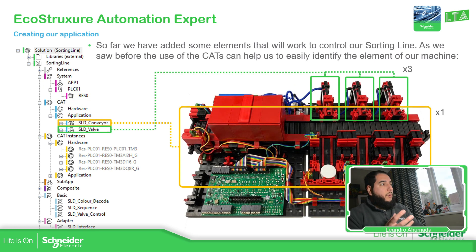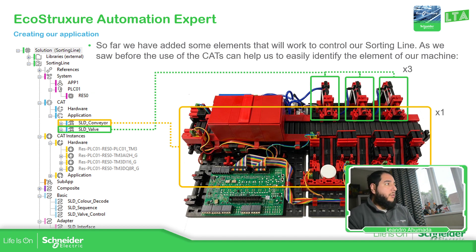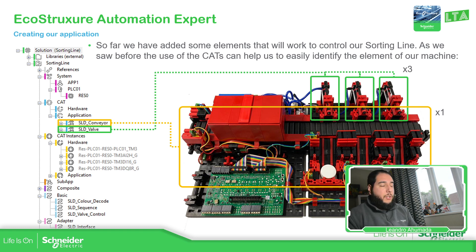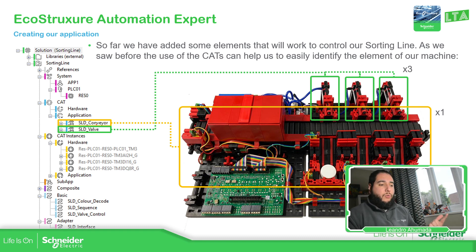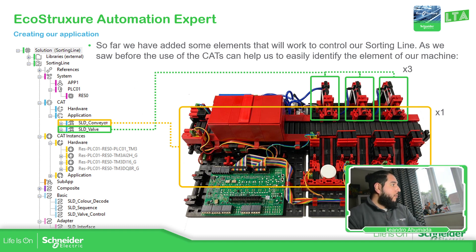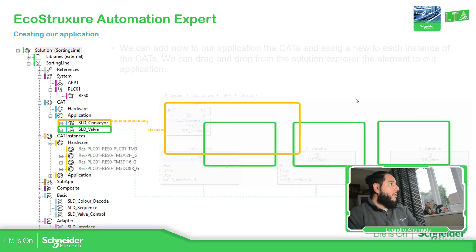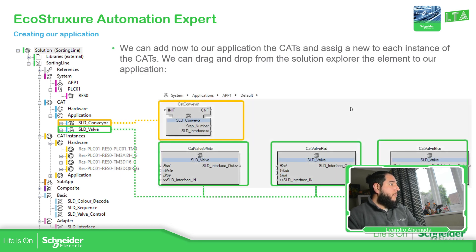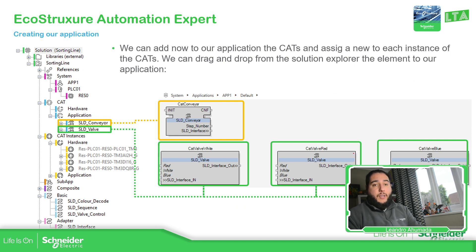Now, in our sorting line we have a specific amount of blocks that we need to use or CATs that we need to use. We have one CAT for the valve and another one for the conveyor. We need to create instance of those CATs in order to replicate what we want to do. We need one instance for the conveyor and three instance of the valve for the three valves that we have. In order to use them, what we need to do is to open the APP1 and then drag and drop each CAT over there.